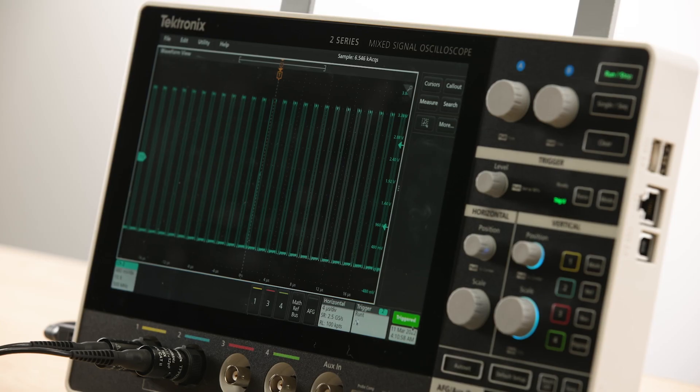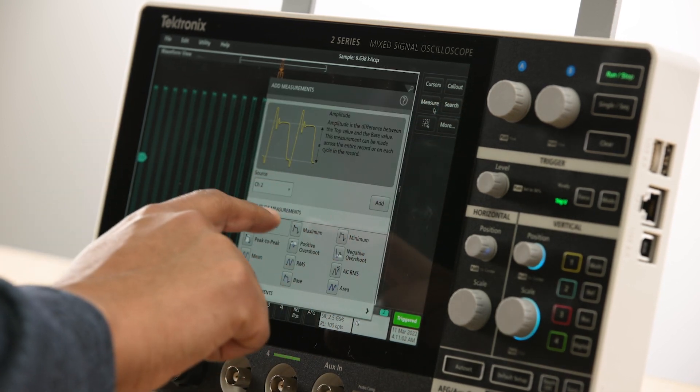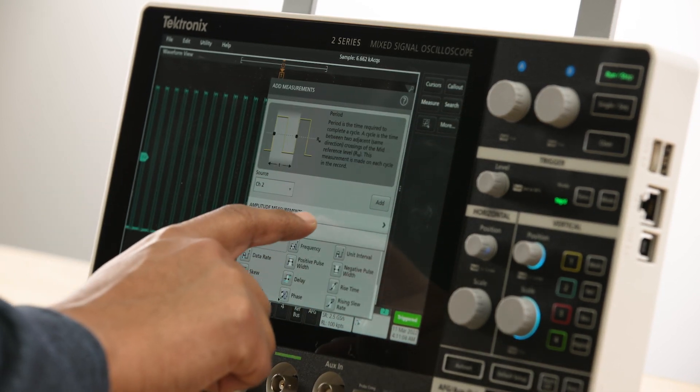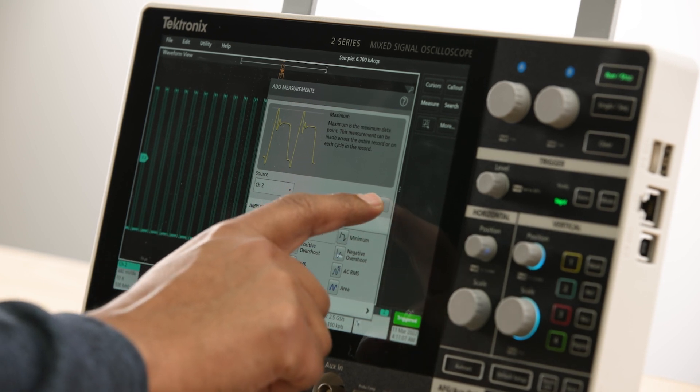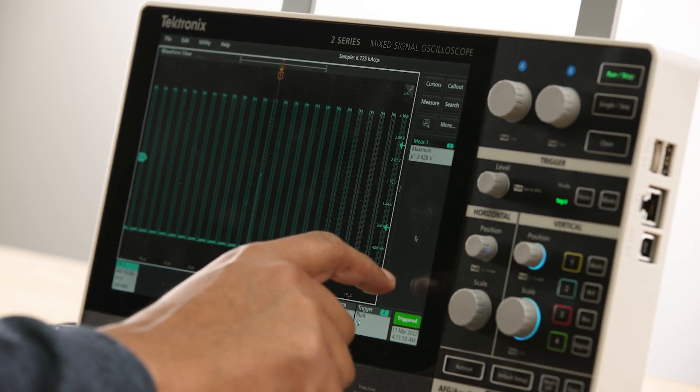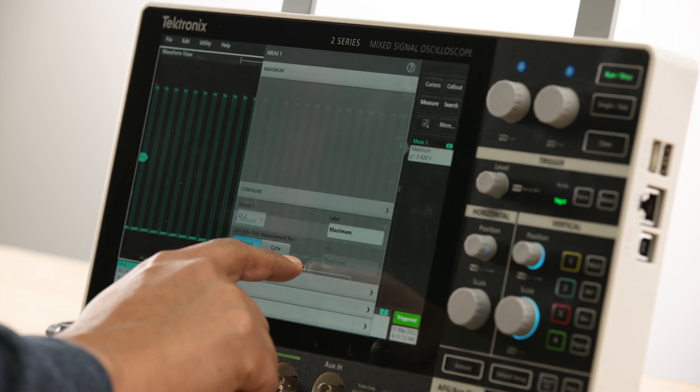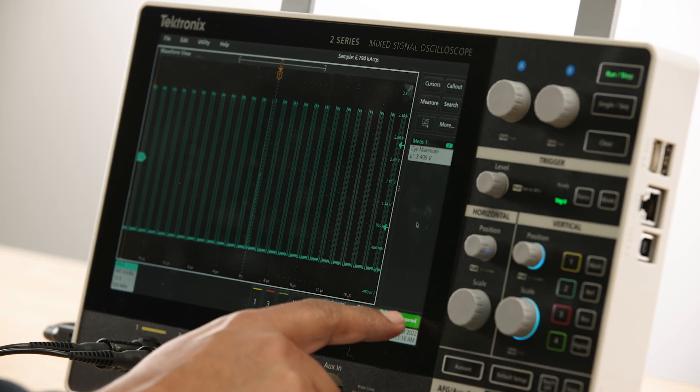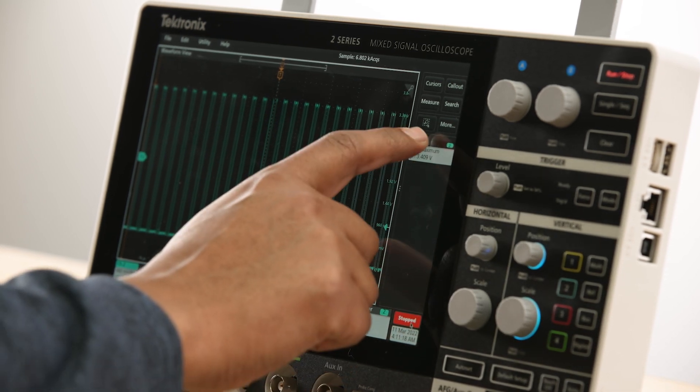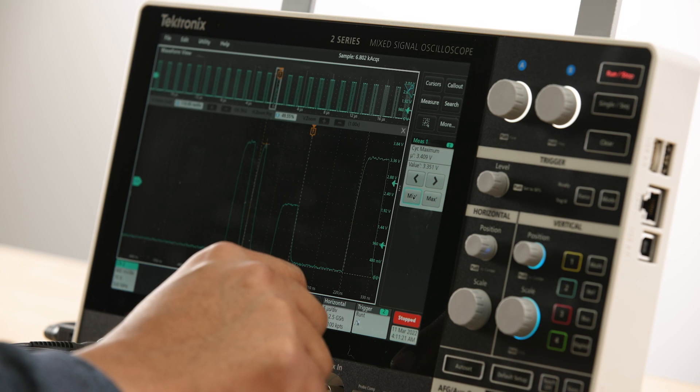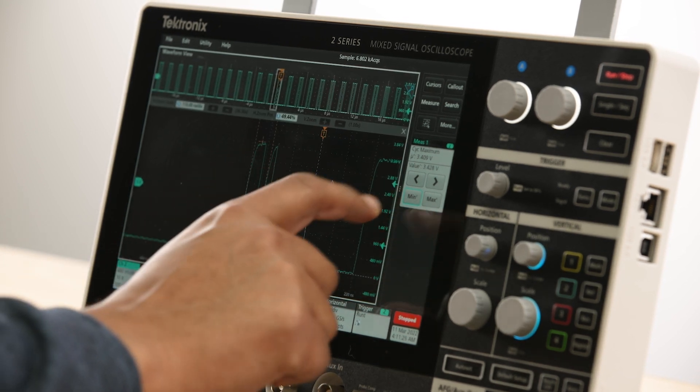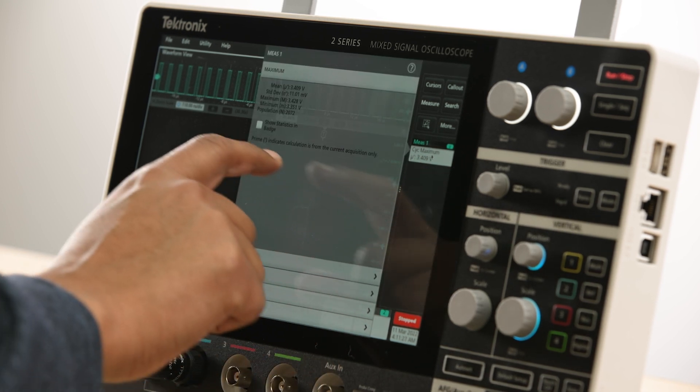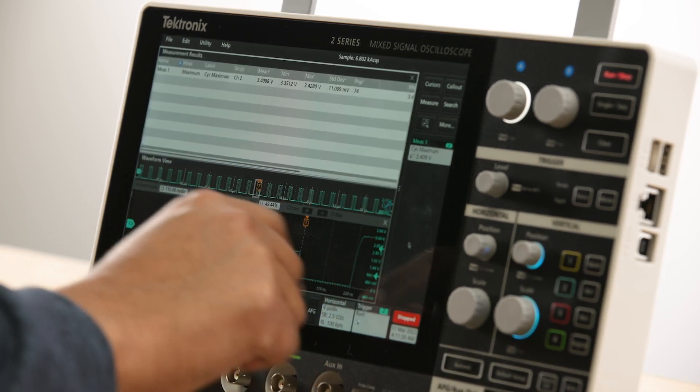The fine and coarse adjustment options enable you to position the cursors precisely on the waveforms. There are 36 automated measurements that can be used to measure waveform characteristics. Measurements can be quickly added to any given source. Unlike other scopes in the market, measurements on the 2 Series MSO are performed on the entire record, resulting in additional statistics that can give you more insights and help you quickly navigate to any measurement location.